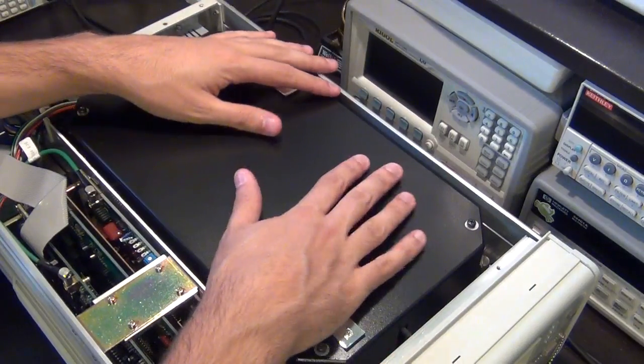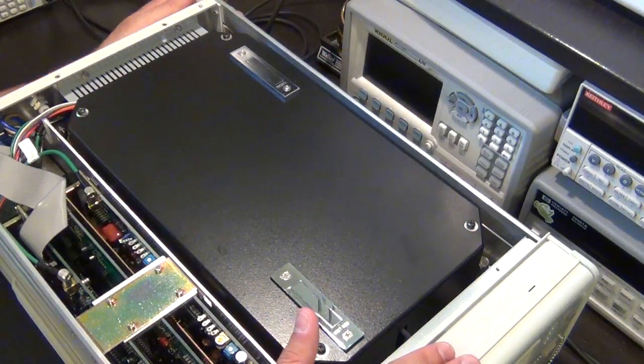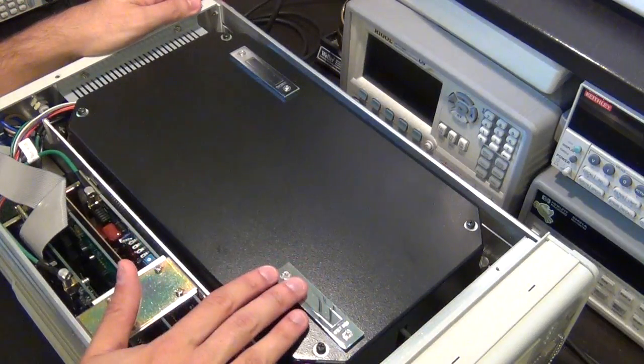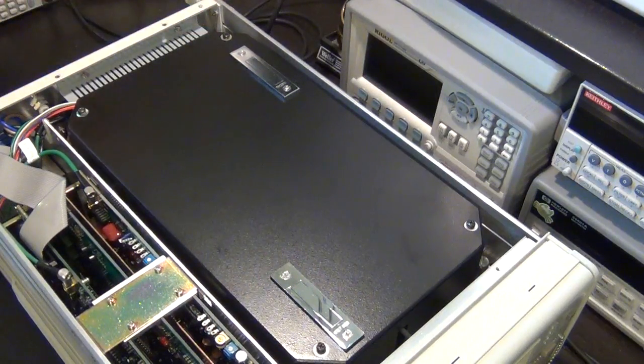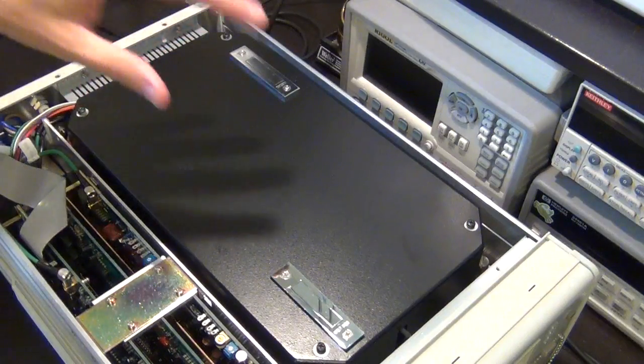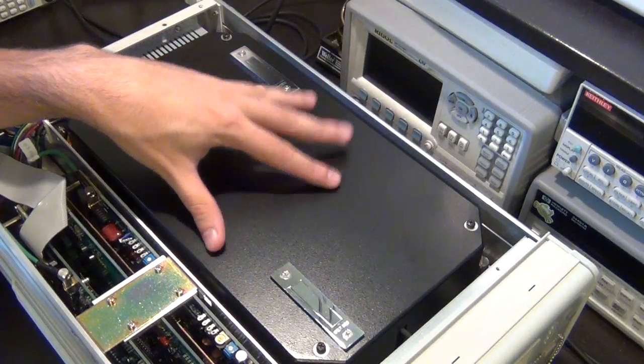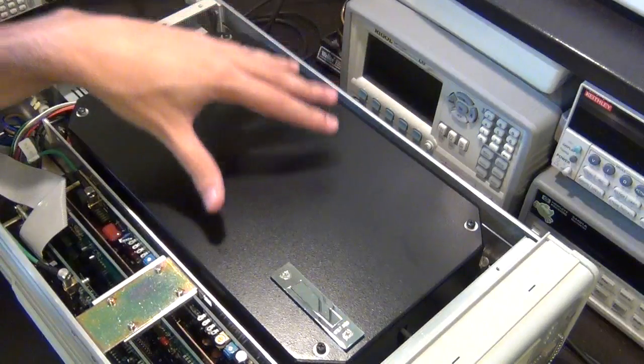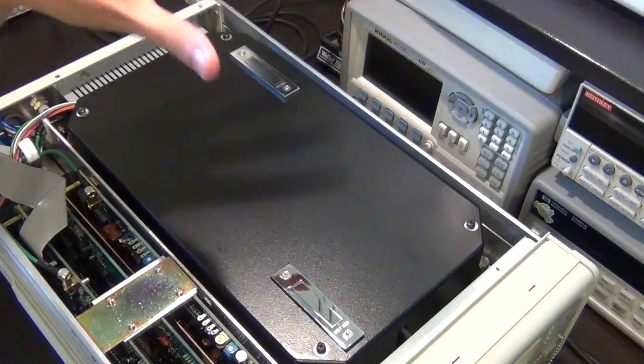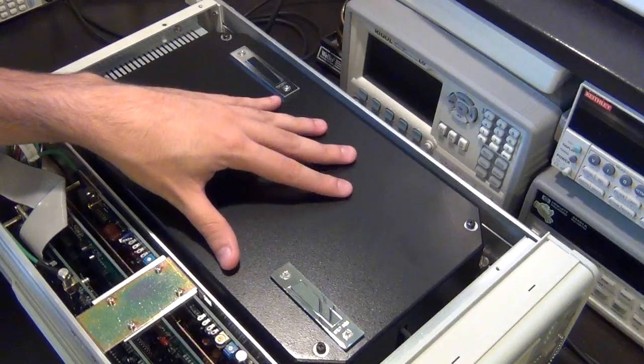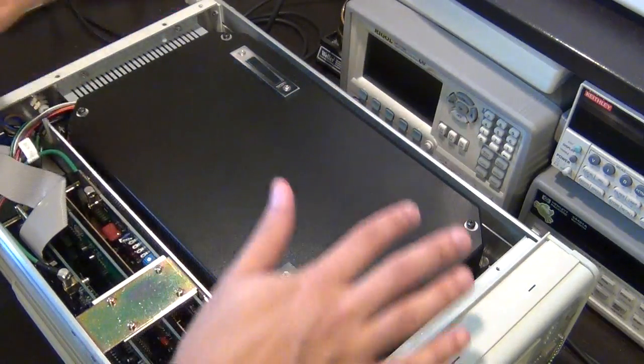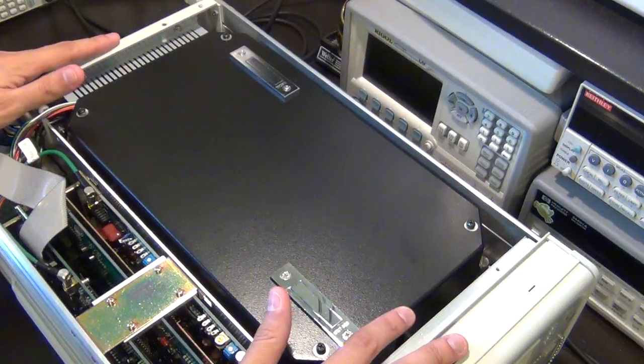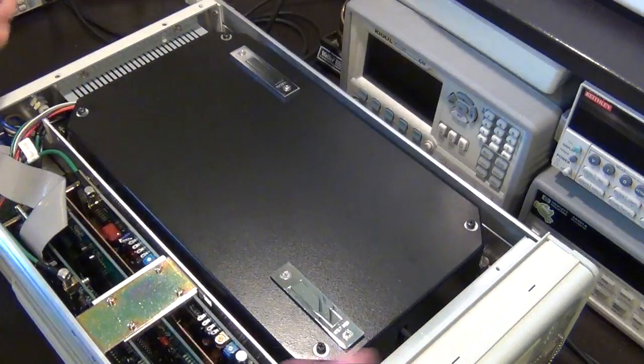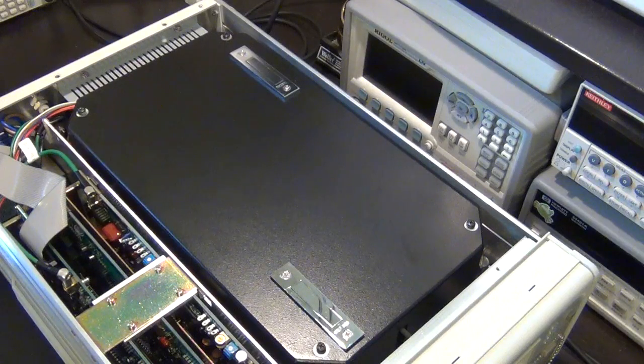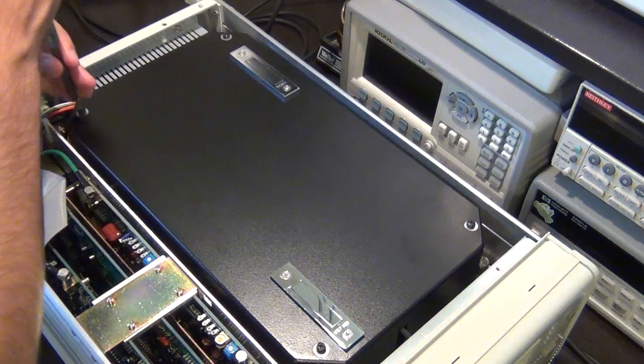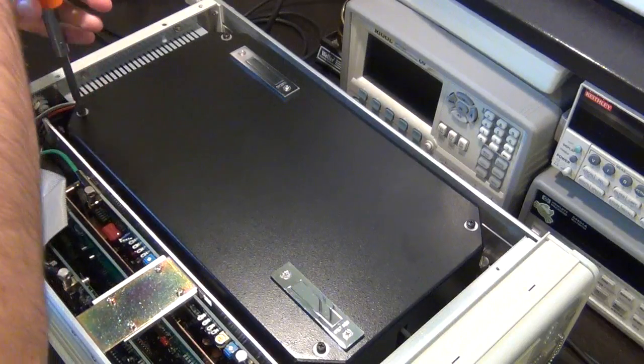But before we take any of this apart, I want to give you a disclaimer. You should never open optical instruments unless you know what you're doing, for 2 reasons. First, there is visible and invisible optical radiation, like lasers, that can come out of instruments when you open them, that can be harmful to your eyes, especially if they are non-visible, because you can't even tell that you're damaging your eyes. The second is that every optical instrument like that, with free space optics, has been very carefully tuned. If you open these up and move them or bang them around, then you're going to take them out of calibration. So you have to be very careful when you deal with this type of equipment.